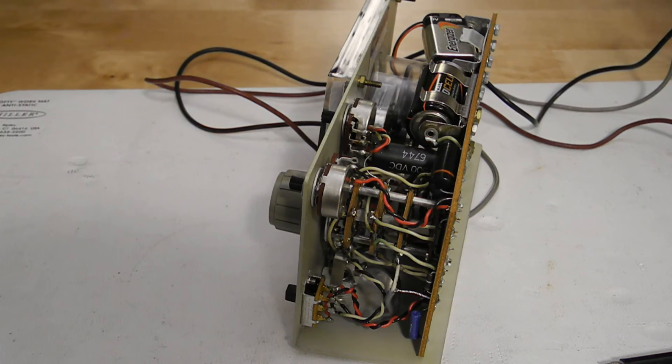The unit is a little hard to work on once assembled. You'll want to disconnect the printed circuit board from the front panel to do any significant work or parts changes.